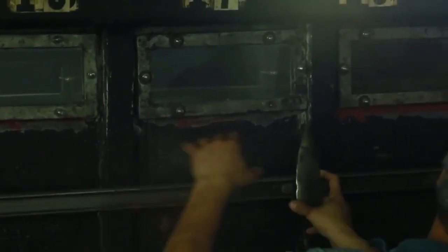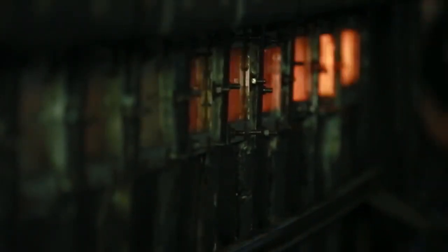Once we've established the flame spread ratings and the smoke developed ratings, we use those numbers quite extensively in our building code regulations, principally in the International Building Code, the International Residential Code, as well as many other codes, including NFPA codes such as NFPA 101 or NFPA 5000. Those codes regulate interior finish materials based on flame spread and smoke developed ratings, and that determines where these materials can be used or whether they can be used at all.